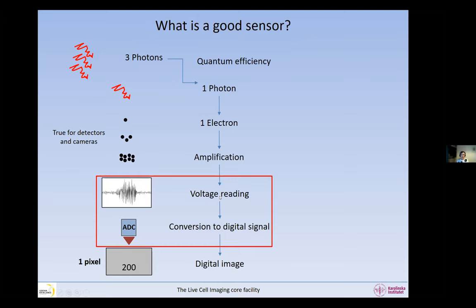We're talking about the dynamic range and bit depth — the way we convert and read the signal. The dynamic range of the sensor is the ability to read dark and bright areas with details and without saturating. We'd like lots of details in dim places and very bright places, and we do not want any saturation or underexposure. Ideally we want a high dynamic range — this is a specification of the sensor, so once you have your sensor, there's not much you can do about it.